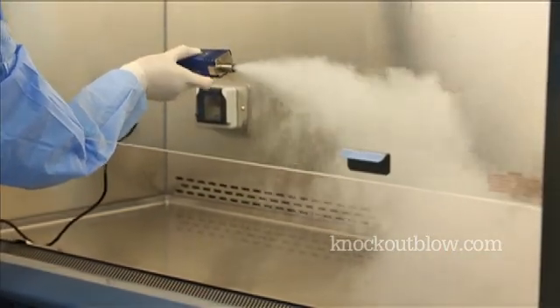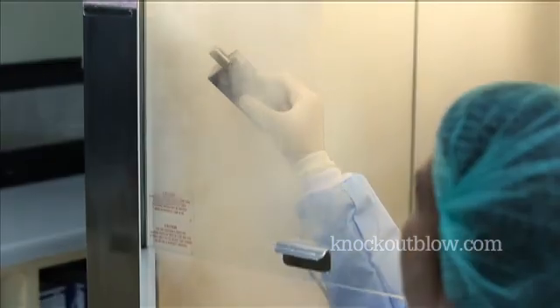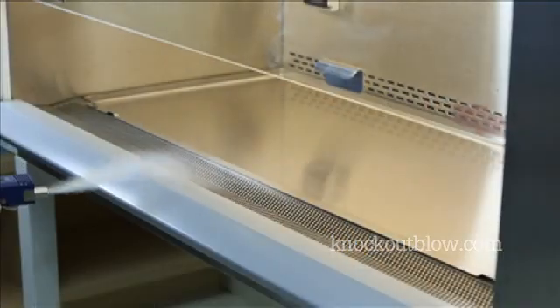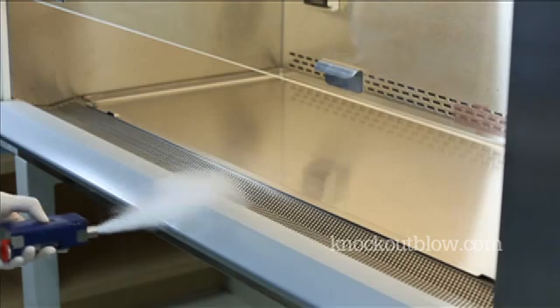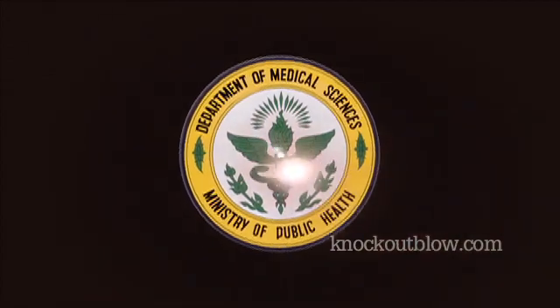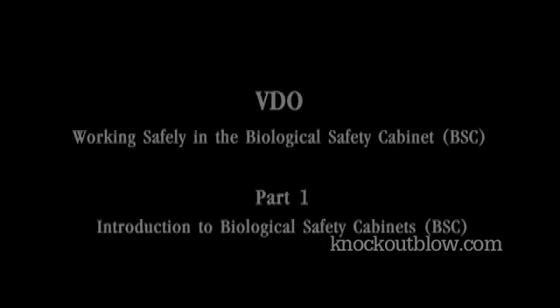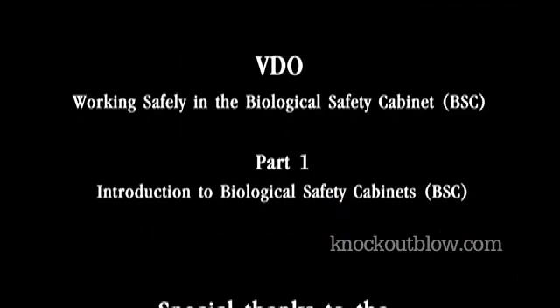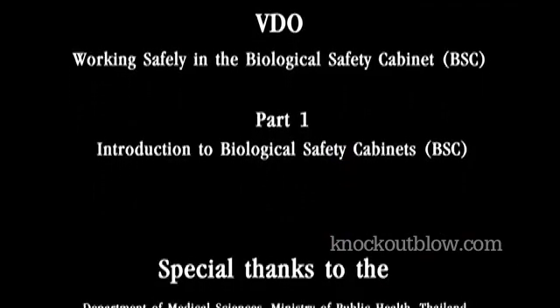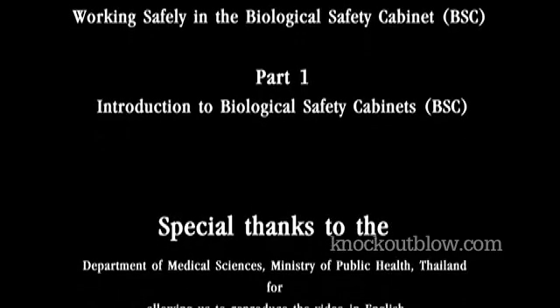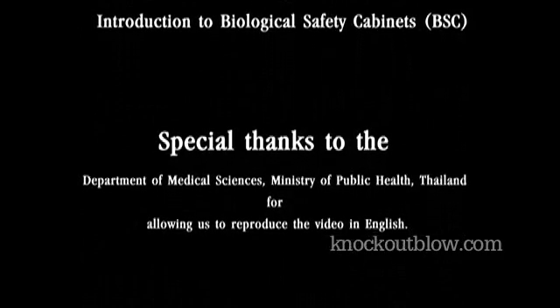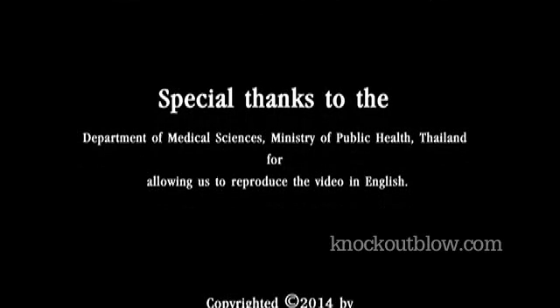BSC field certification tests must be performed on each cabinet at the time of installation and at least annually or whenever the HEPA filters are changed. Maintenance repairs are made to internal parts or when the cabinets have been moved.